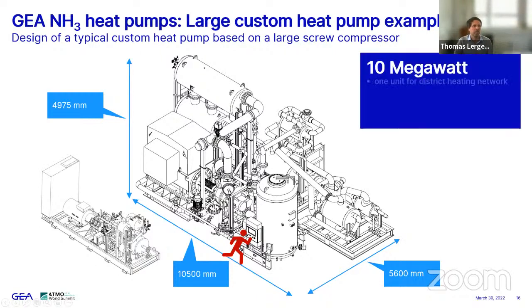This is coming from a very large district heating project, 10 megawatts per unit, for a district heating network in Finland. They have a liquid heat source, probably from a cooling cycle, and they're cooling this down with the unit from 27 to 21 degrees Celsius. And on the hot side, the return temperature is 47, and then the heat pump heats it up to 85, and this is the supply temperature that's going to the consumers.